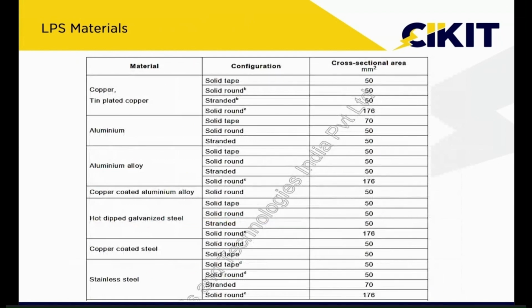This is the recommendation provided by 62305 for selecting the material dimensions. Here you can observe that we can use copper, aluminum, dip galvanized stainless steel, copper coated steel, and for each and every material they have provided different configurations also. So it is not like that we have to go for only rod. We can go for strips, or even stranded conductors like cable also. For each material and for each configuration, they have provided what should be the minimum cross-sectional area. So these values are minimum cross-section areas.